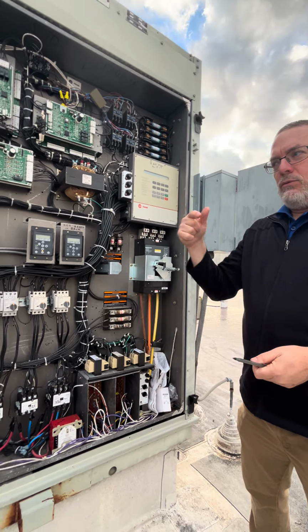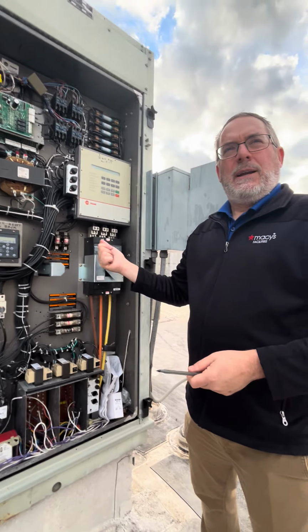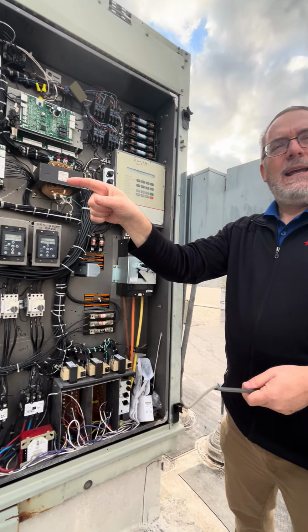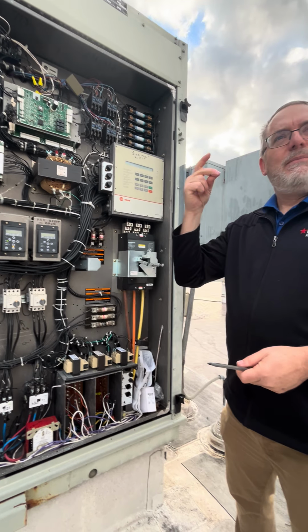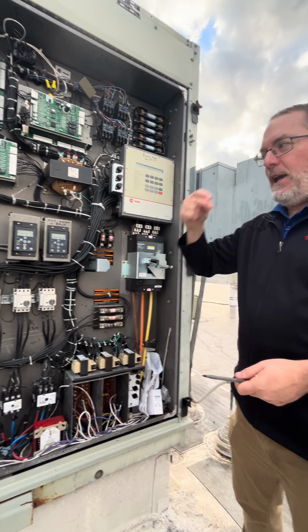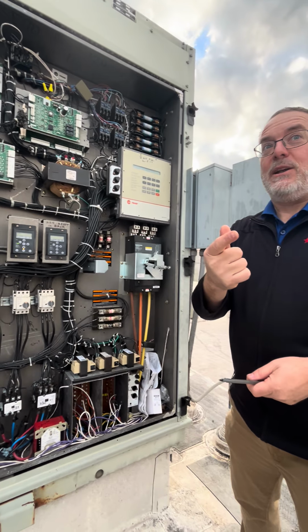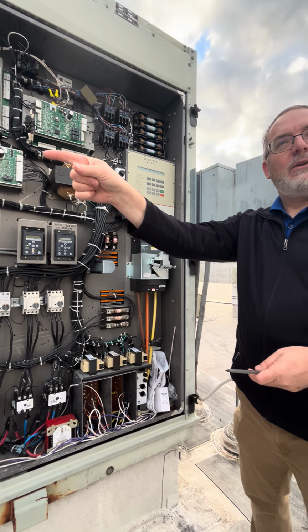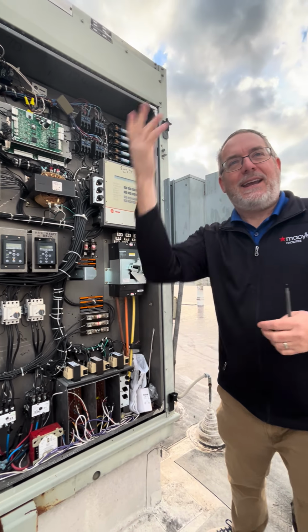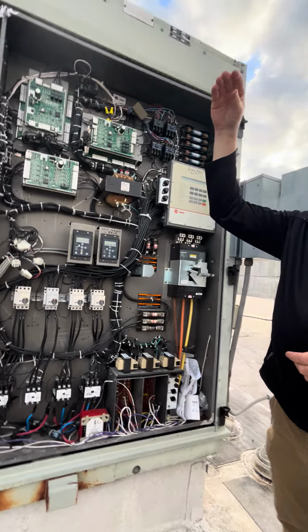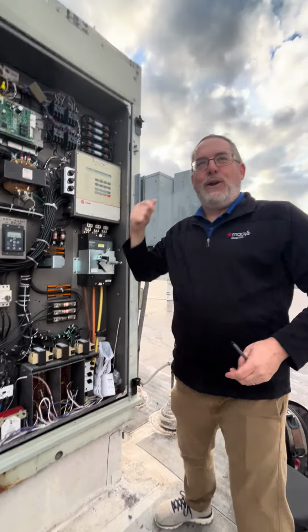So now I've got 2, 3, 4 stages running. I've got dehumidification, I've got condensate. Now all of a sudden I'm 1-2 degrees below set point and I have to shut this unit off. I didn't run long enough to dehumidify, and now I've got a lot of condensate sitting in there that's back in the airstream, and you watch that humidity go up. Then you start it off, you bring it down, and then you turn it off and it goes right back up.